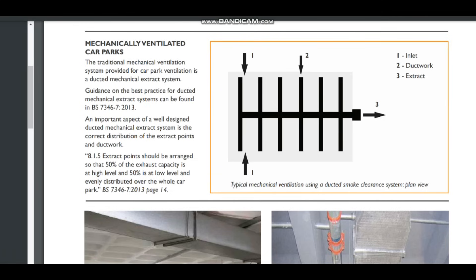Guidance on best practice for ducted mechanical exhaust systems can be found in British Standard BS 7346-7:2013. Under clause 8.1.5, it states that extract points should be arranged so that 50% of the exhaust capacity is at a high level and 50% is at a low level, evenly distributed over the entire car park.